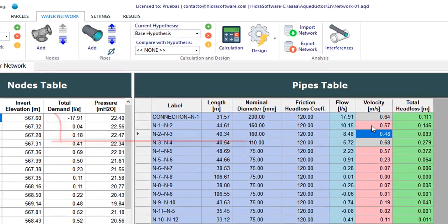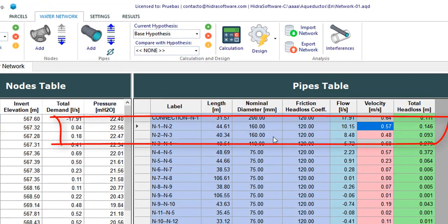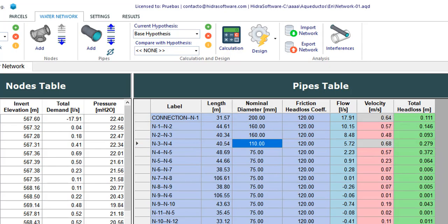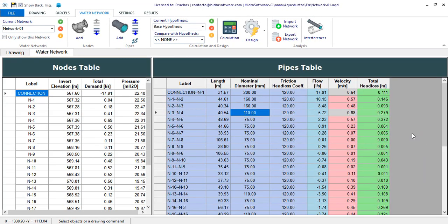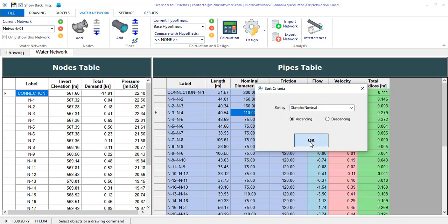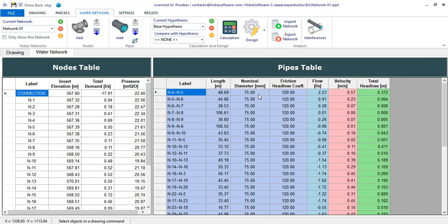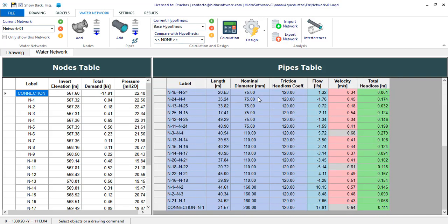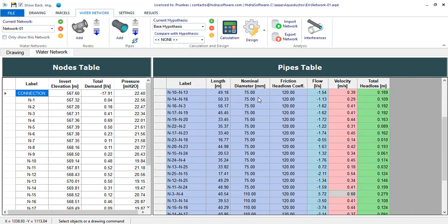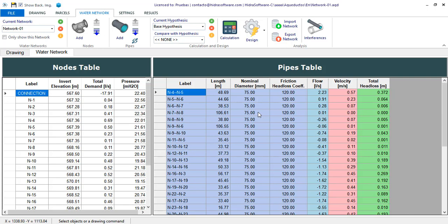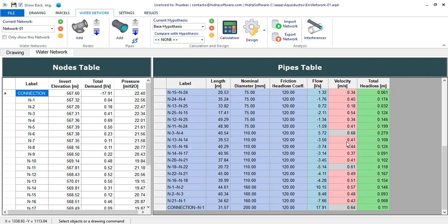While others, like these, could have a lower diameter in order to improve the maximum velocity, it is a matter of refining the design according to our specific criteria. One option available in these tables is to order nodes and pipe sections according to a property. For example, if I want to sort by diameter, I double click on the header and this dialog is shown. In this case, with the nominal diameter property pre-selected, you could well change to the one of your preference. I keep ascending order and click OK. And there we have them. It just remains to make the adjustment to these pipe sections to resolve, if necessary, the issue of low velocities.